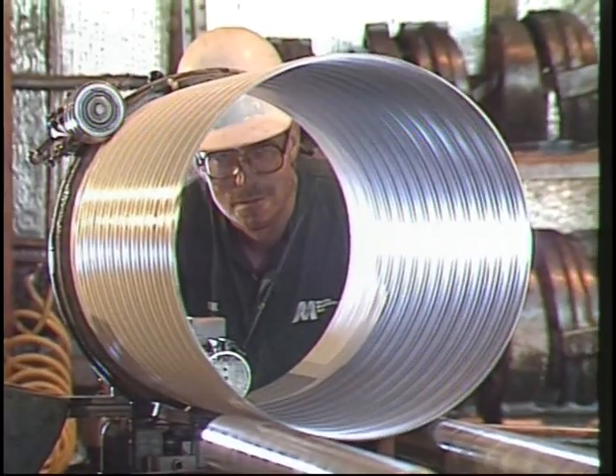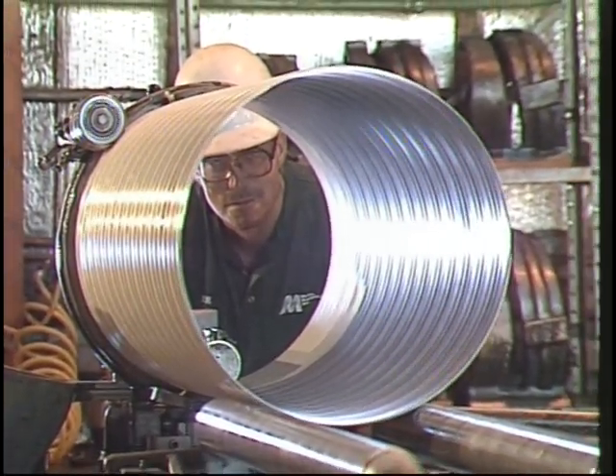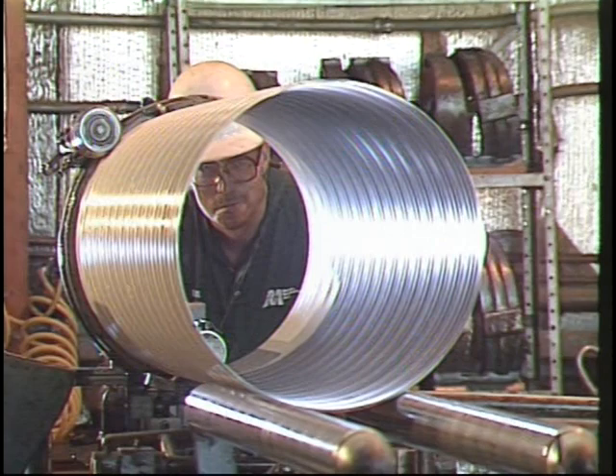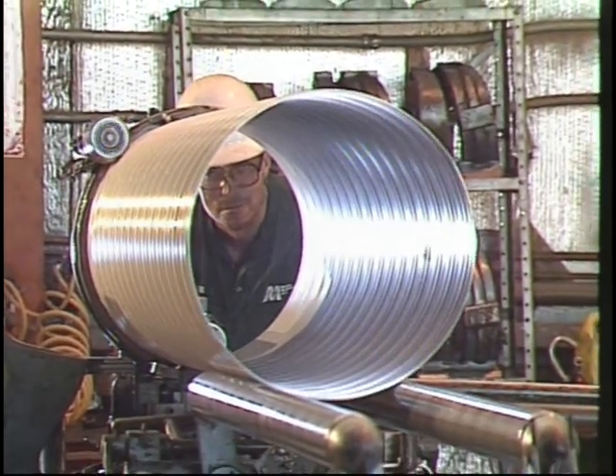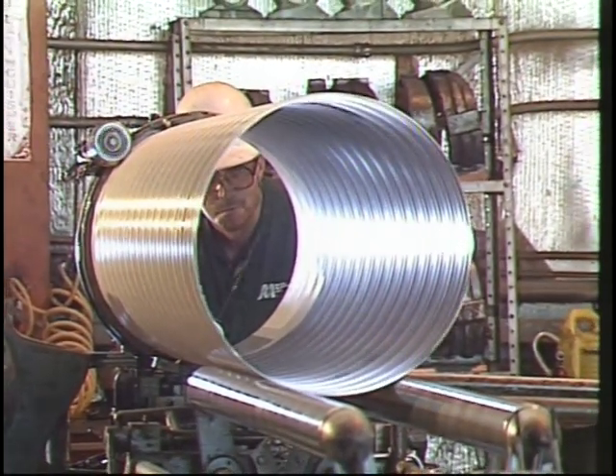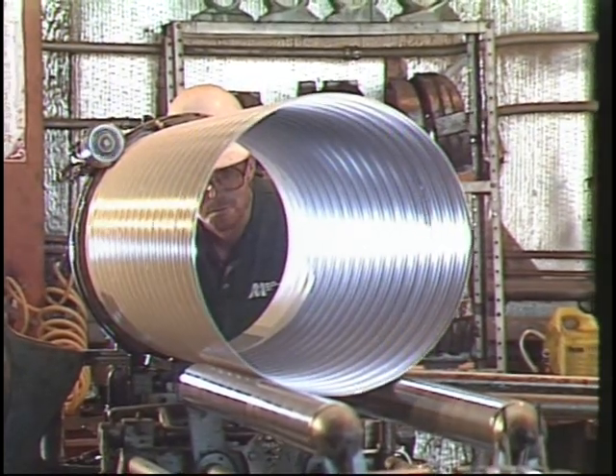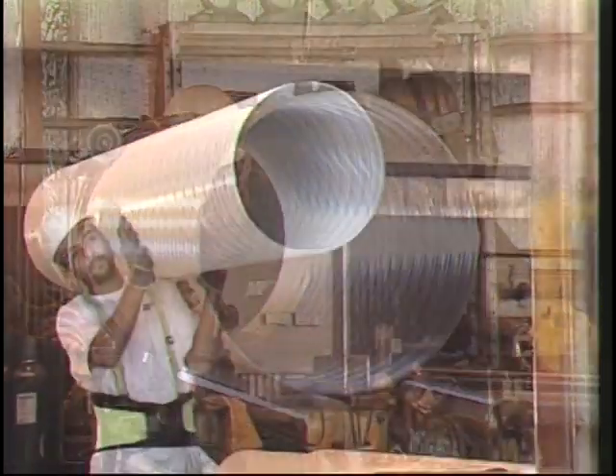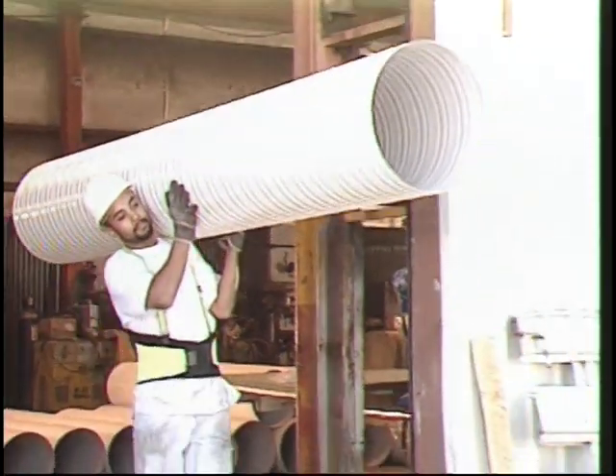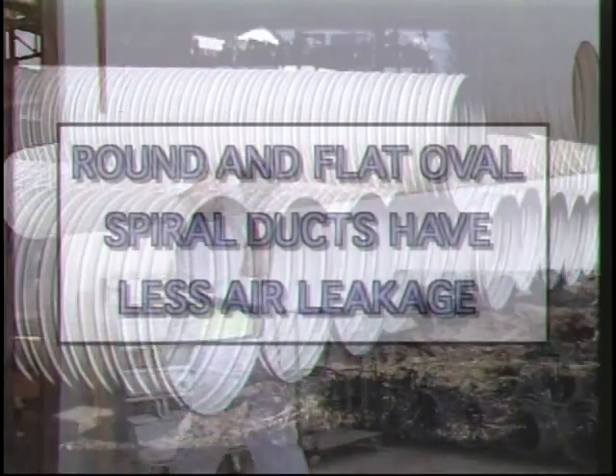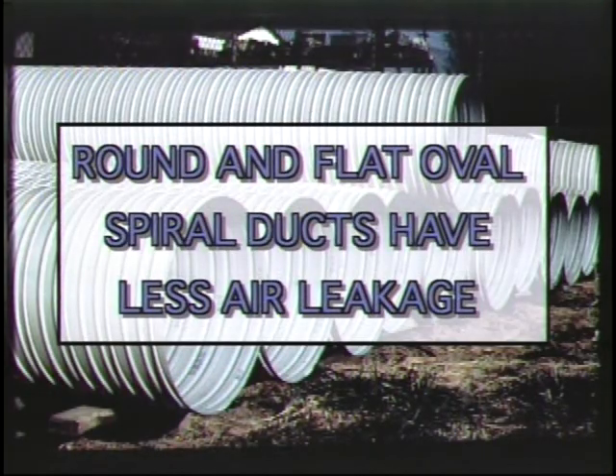Some of the reasons for lower costs of spiral duct systems is that spiral round and flat oval ductwork can be made in exact lengths and in longer lengths that are limited only to what can be handled and transported. Because round spiral duct is lighter, it is easier to handle and to install. And with longer lengths, there are fewer joints connecting the duct sections to leak system air.